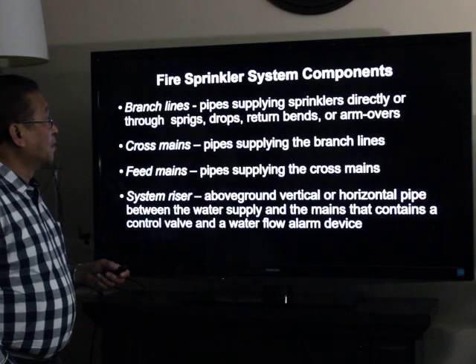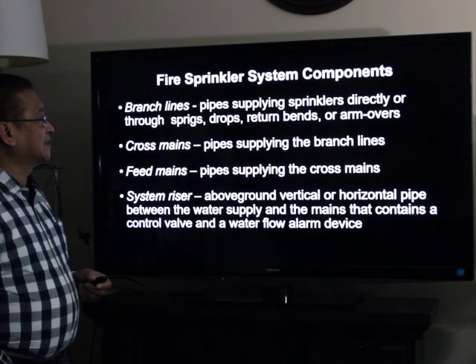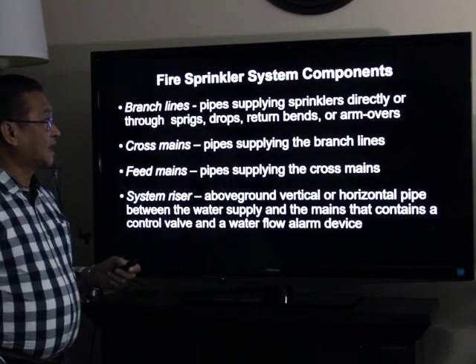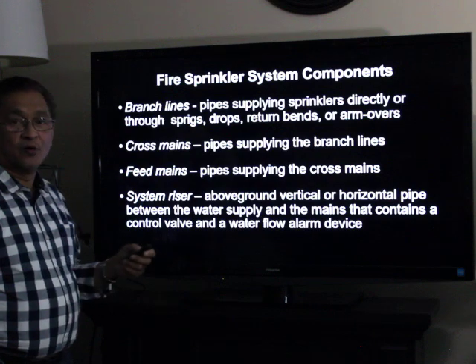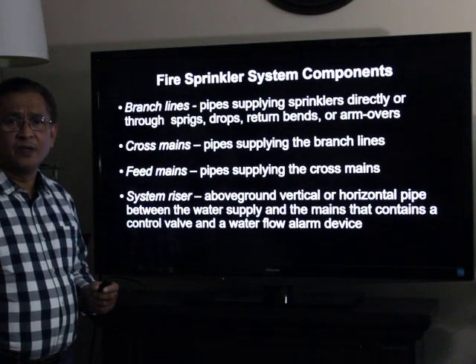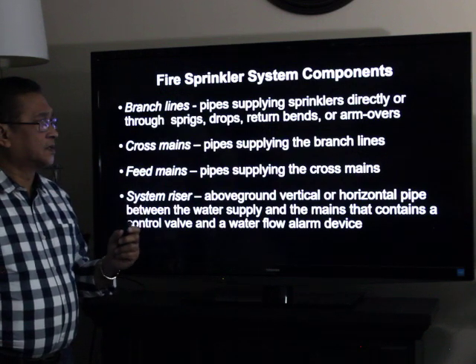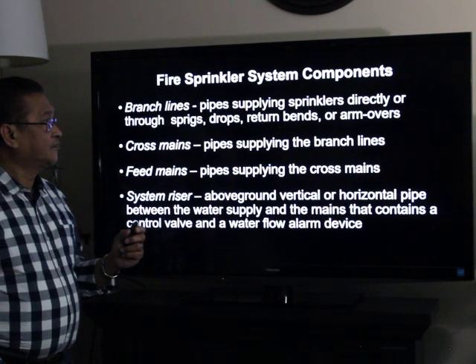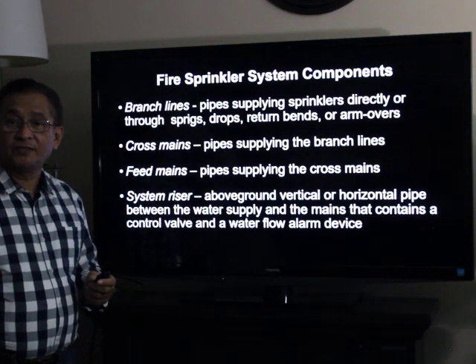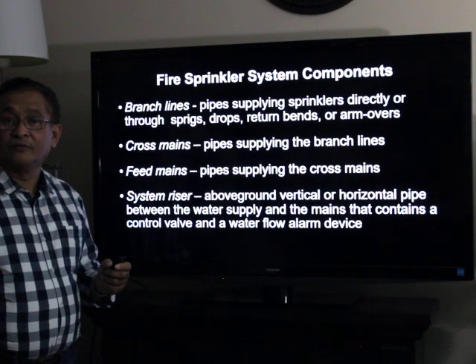Fire sprinkler system components: branch lines are the pipes supplying sprinklers directly or through sprigs, drops, return bends, or arm-overs. Sprigs are short vertical pipes rising and leading to the upright sprinkler. Arm-overs are extensions to the end of the branch line leading to sprinklers located either above or below the ceiling.